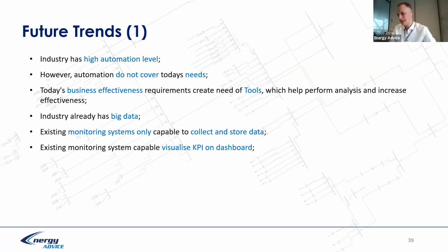And existing monitoring systems are also capable of visualizing KPIs on a dashboard. Yes, we can divide one number by another if both are measured values. But in the boiler system, we have a complication: we don't have the fuel calorific value. Fuel calorific value would probably be known only after 1-2 days, or a couple of hours after the fuel is burned. Because of that, the dashboard data showing that the past was bad is not important. We don't need to understand that the past is bad, because we need to live now and control and optimize now.